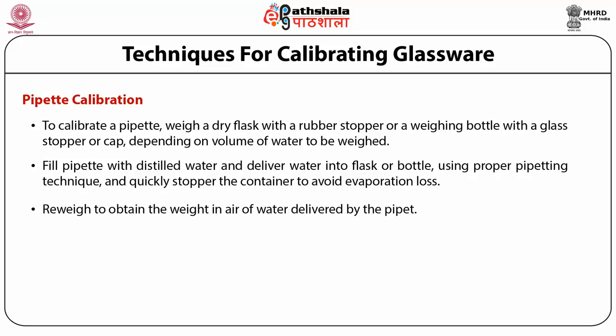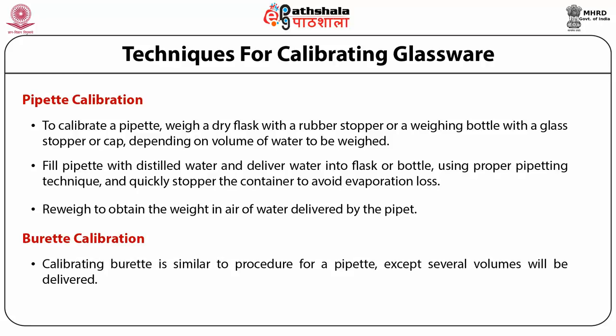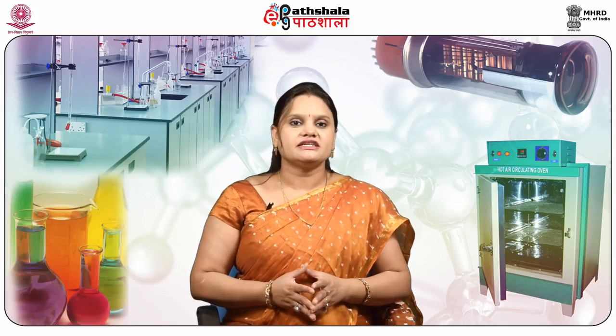For burette calibration, the procedure is similar to that for the pipette, except several volumes will be delivered. The internal bore of a burette is not perfectly cylindrical and will be slightly wavy, so the actual volume delivered will vary both plus and minus from the nominal volumes marked on the burette as increased volumes are delivered.